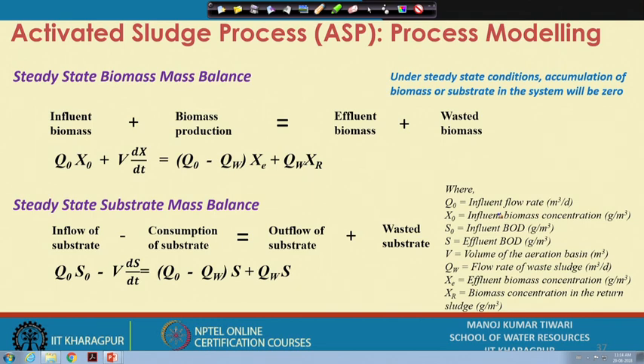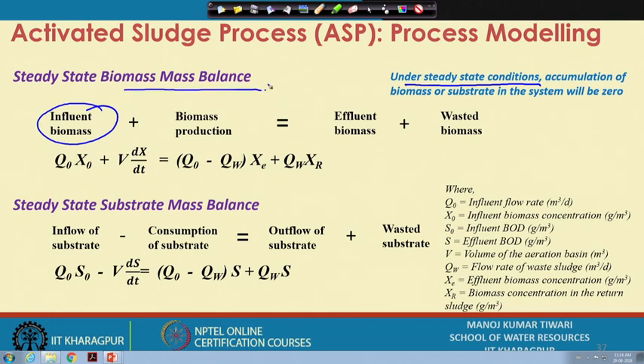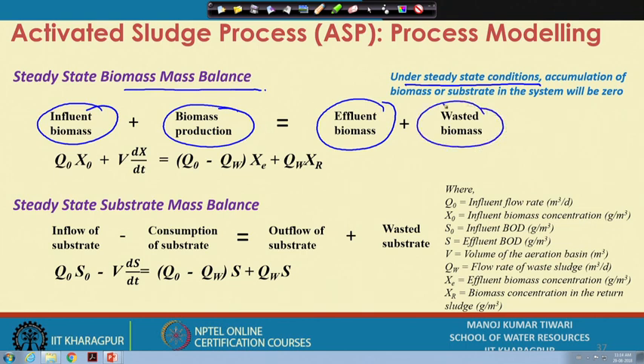We are considering mass balance under steady-state conditions. The accumulation of either biomass or substrate in the system is not taking place because it is a steady-state condition. Looking at the steady-state biomass mass balance, the influent biomass coming into the system plus biomass being produced would be equal to the biomass leaving with the effluent and biomass which is being wasted.